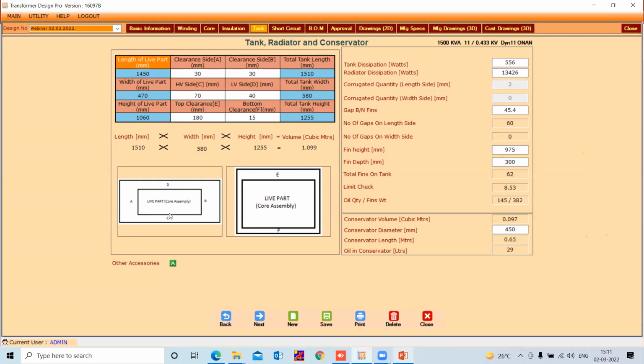There are two images. The first image you can consider like a top view of the transformer, and A, B, C, D are the clearances from live part to tank enclosure. And these clearances are available in this table, which can be editable. And the second image you can consider as a side view, and E is the top clearance and F the bottom clearance. That value is also available here to edit. And based on that, your transformer tank LBH is calculated over here. The tank length, width, height, including your volume in cubic meter.